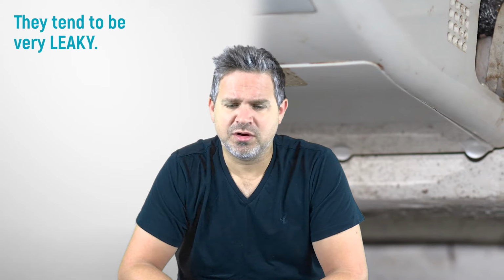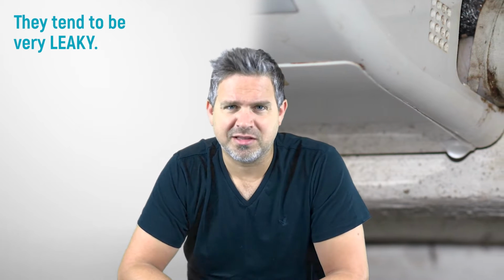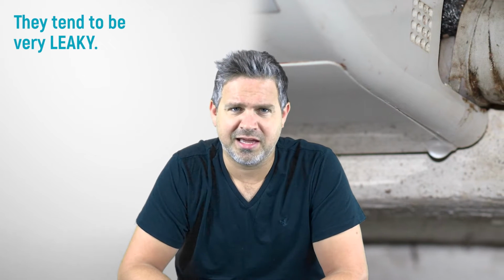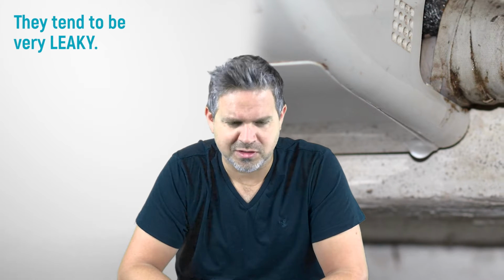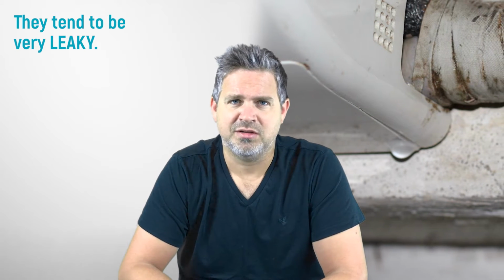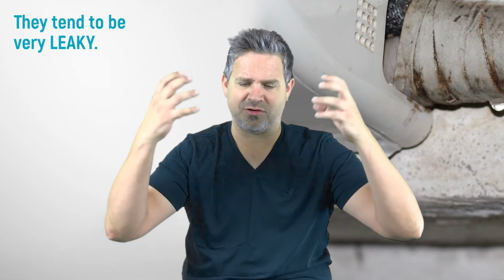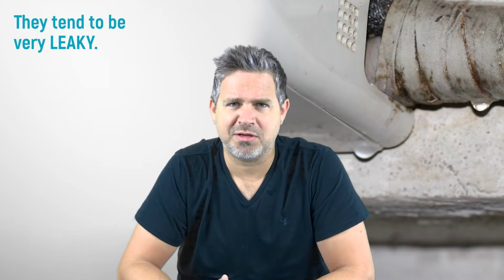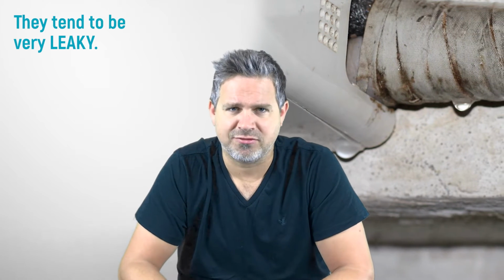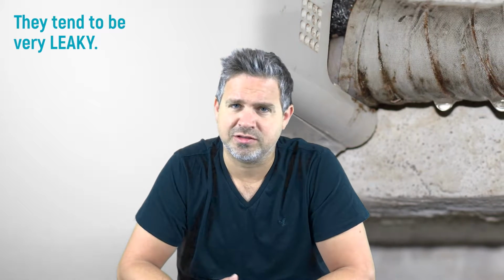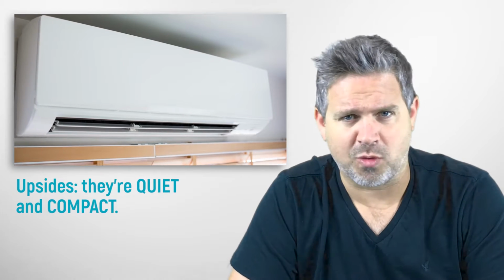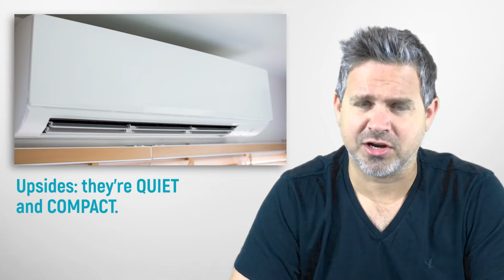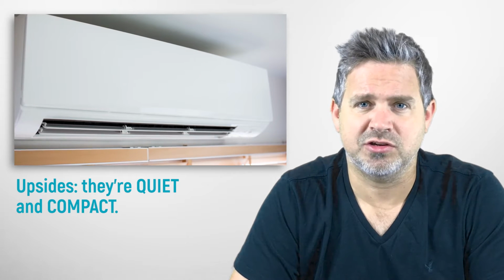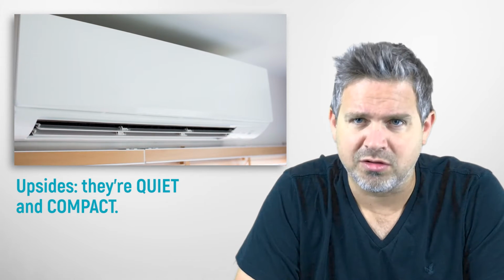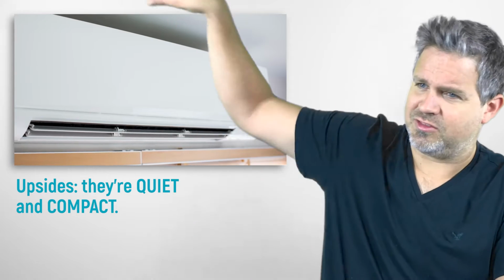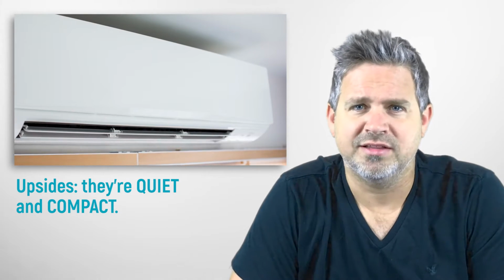They can also leak sometimes. We installed hundreds of them, and we found that some manufacturers, not all of them, but sometimes they'll start leaking, they'll start dripping. I'm not a big fan of them, again, unless you have to, unless it's your only choice. On the upside, they're super quiet, right? They're not very noisy, which is a good thing. They're relatively small. People sometimes don't like this unit sitting on their wall, so that's a bit of a downside.